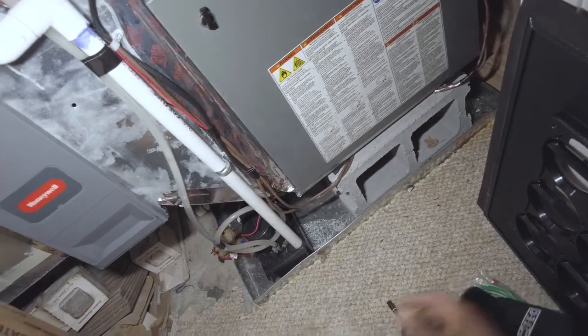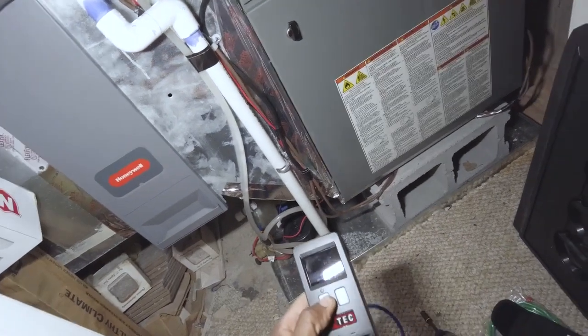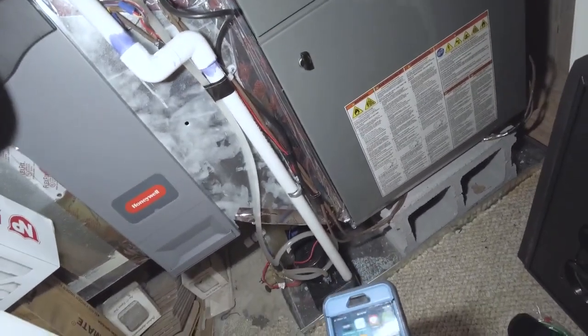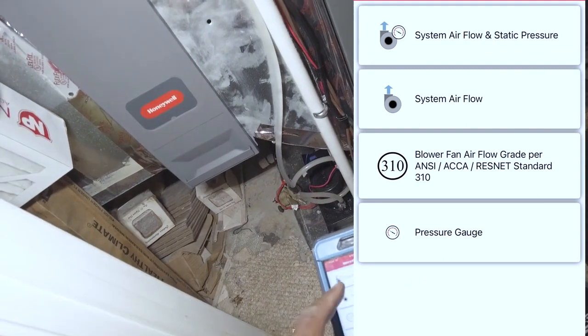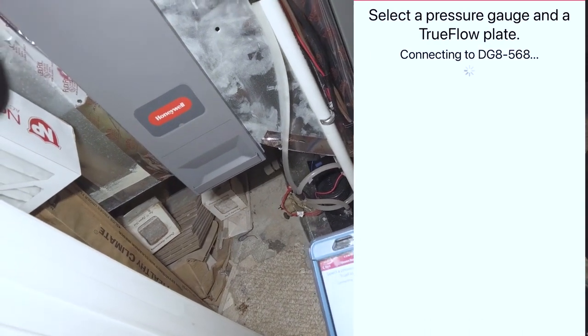The cool thing about this is it's pretty much foolproof the way they set this app up. We're going to turn on the manometer — hold down the power button for five seconds, that's three seconds — then turn on the TrueFlow. Grab the app here. TrueFlow Grid — as you can see, I'm going to do system airflow and static pressure, so select gauge. It literally walks you through everything.